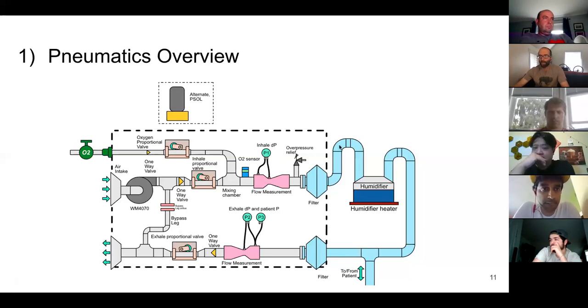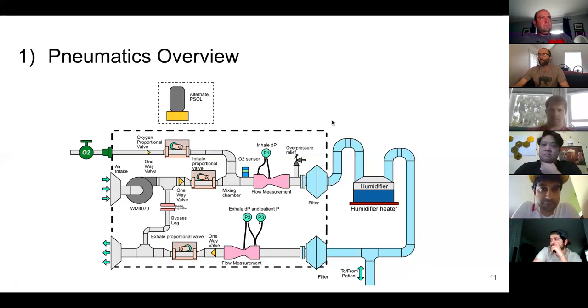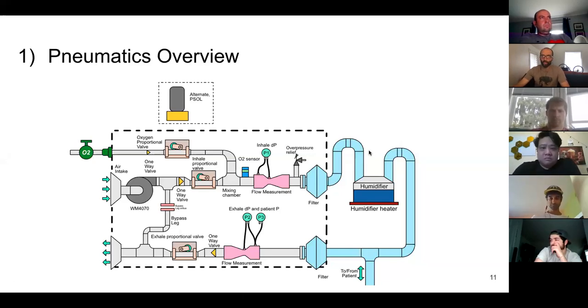We've moved the humidifier external to the design. Some of the feedback we got was that mostly the humidifiers are standalone units. I think we're not planning on, and maybe this needs to update in the PCB, even having the heater control. We were talking about having the heater potentially be powered by the ventilator, but have everything else be standalone. That's still something we should nail down, but it's not as big a priority as some of the other stuff. It's good to leave it as an option but not spend a lot of time on it. At this point, taking it out doesn't save a lot of cost and adds time, so it's still in there.